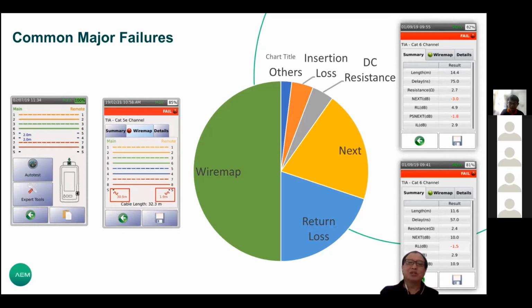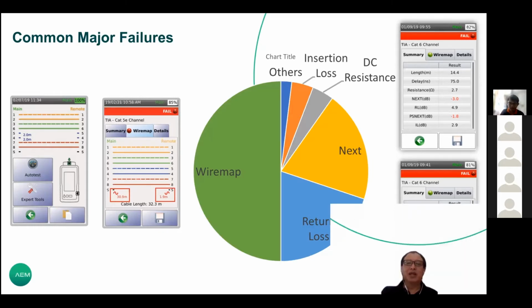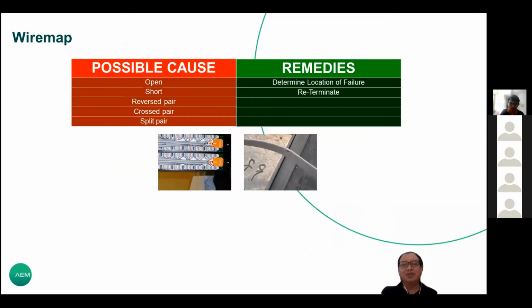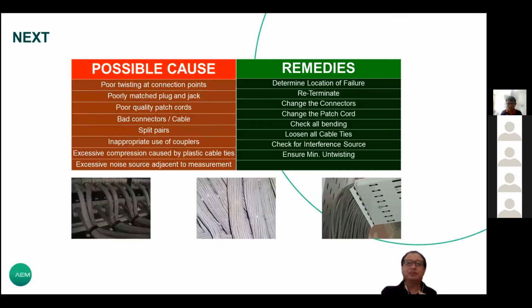Shielding can also cause wiremap failure. Wiremap is quite easily resolved. Basically, you have to find out what the issue is, where the location is, and you can do the re-termination. But if your cable is cut or broken, do not join it back. You have to replace the whole cable. So this is the more common remedy for how to resolve a wiremap issue.